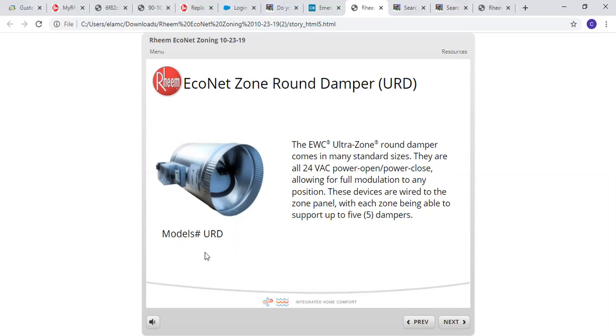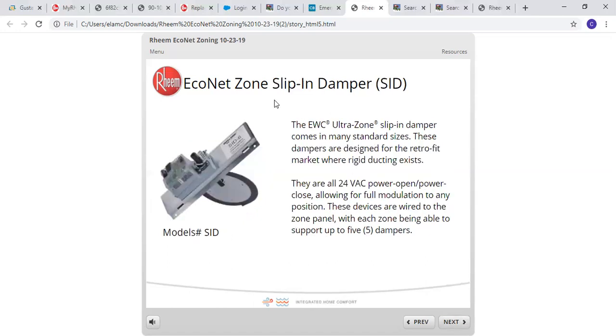This is the round, which is what they call the URD. This is the EWC Ultrazone round, 24 volt, power open, power closed. It allows for full modulating to any position. These devices are wired directly back to the zone panel itself, with each zone being able to support up to 5 dampers per zone. This is the Econet slip-in damper, the SID. These dampers are for the retrofit market where rigid ducting exists. They're 24 volt, power open, power closed.